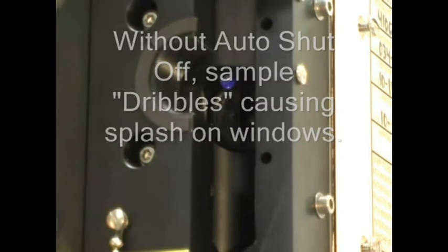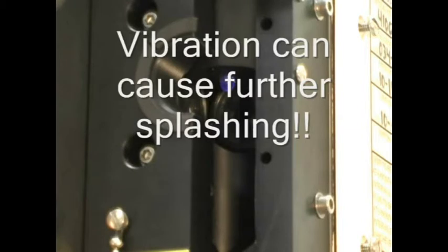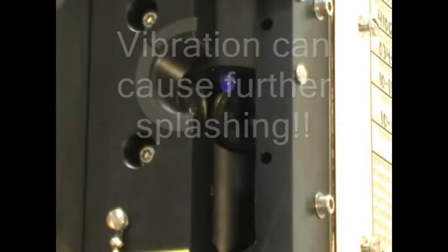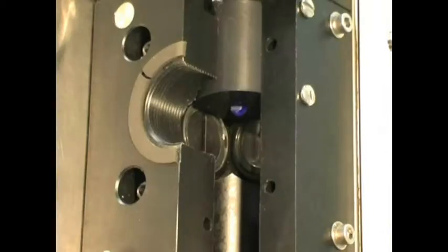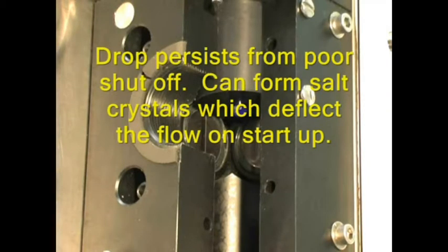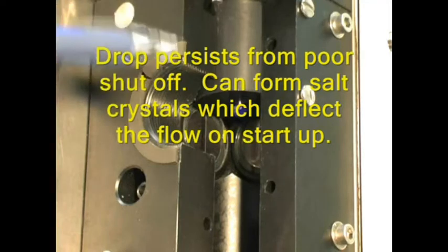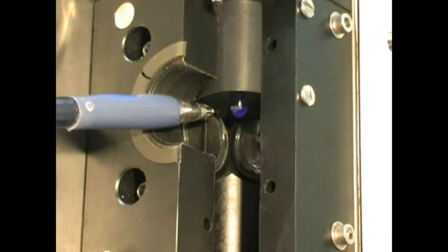Water on the windows can leave deposits that affect the optical performance of the monitor. If this were salty water, as is often the case in oil production brines, the hanging drop can form salt crystals which can deflect the flow. Vibration, as is typical on shipboard applications, can cause further splashing on the windows. Here's another view of a persistent droplet and some splashing on the windows.